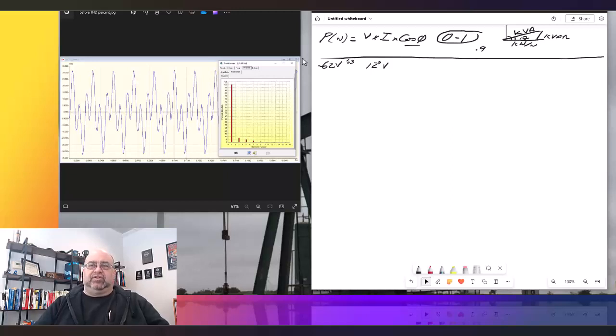It was difficult to do the actual panels. So we're going to have another site that we're doing, and that we're expecting to be much, much higher. So in any case, we take a look at this, and we want to clean this stuff up. We got 31 amps peak right there, which is going to be roughly 24 amps, right? So just because of the noise and everything else. In reality, it was telling me the third harmonic is 14 amps because of everything else. So let's take a look at that.